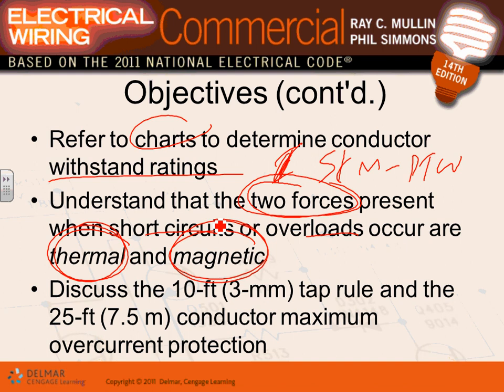So what do you need the circuit breaker to do? Open fast, so it stops the shaking and baking. Why? Otherwise, that thing is going to blow out off the wall and burn itself. So that's the term they use when they have a short circuit condition or ground fault: shaking and baking. The baking happens with I squared T. That's how they measure it. They take the current, square it, and multiply by the time in seconds, and that's the baking.